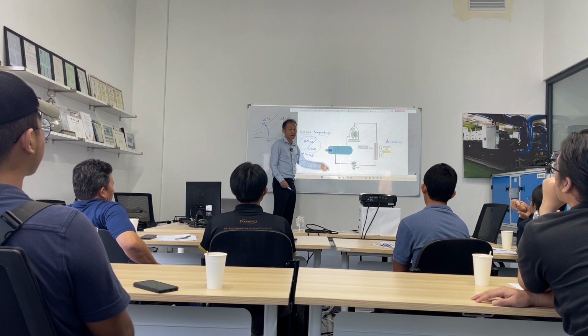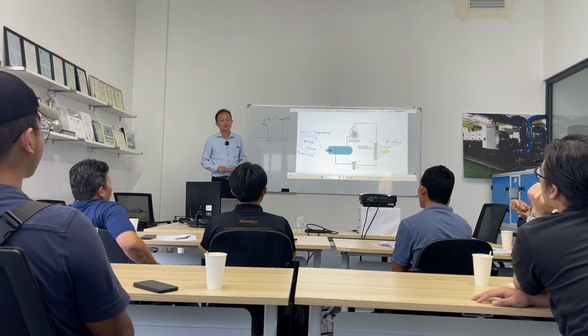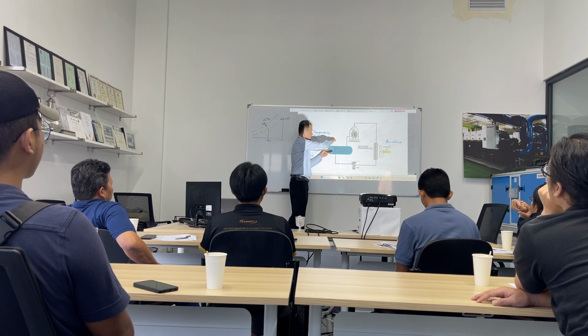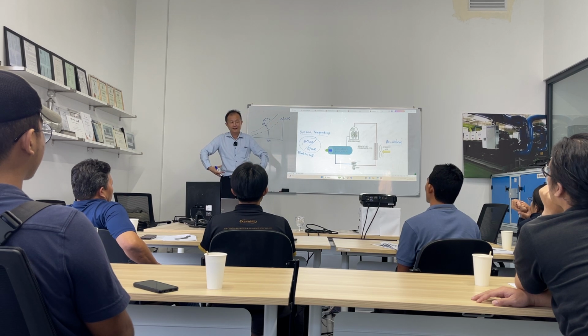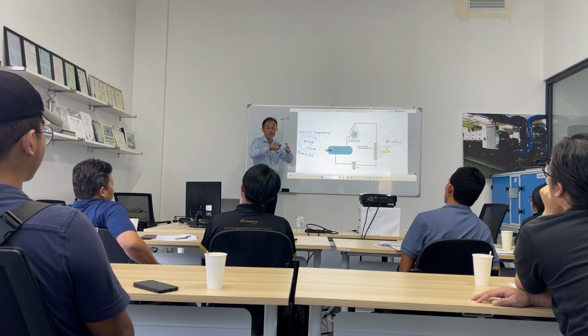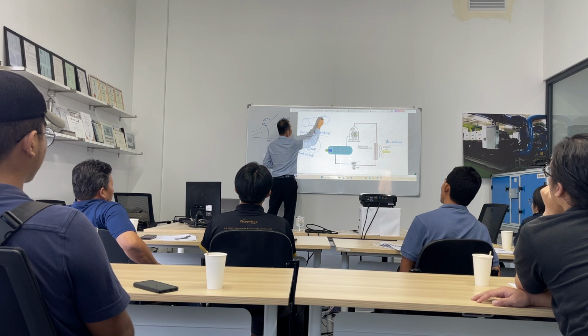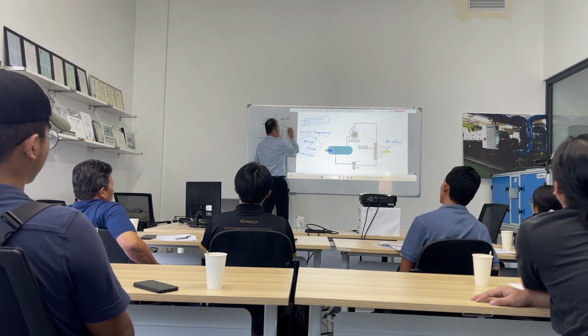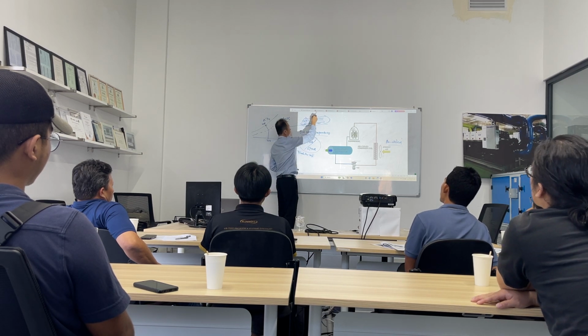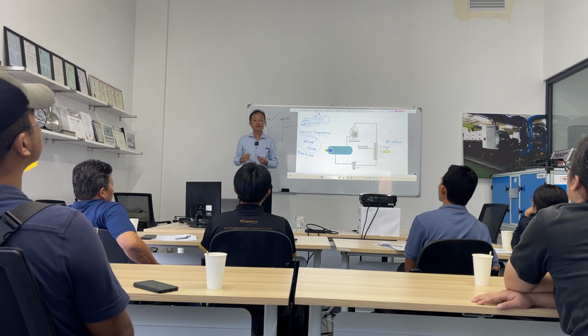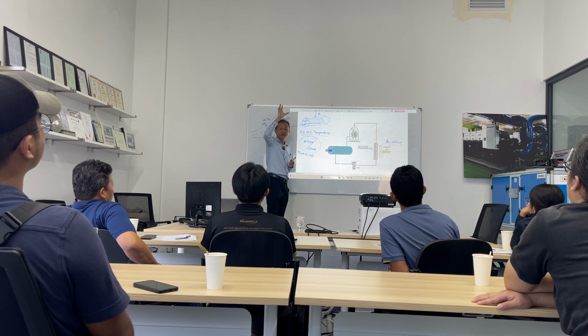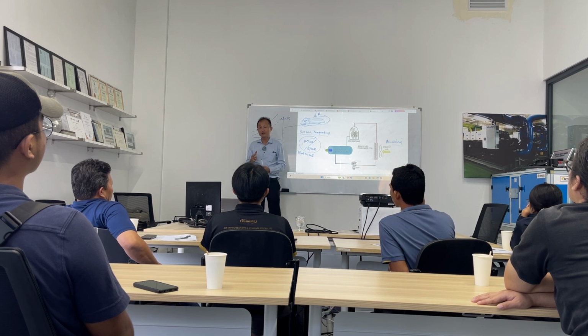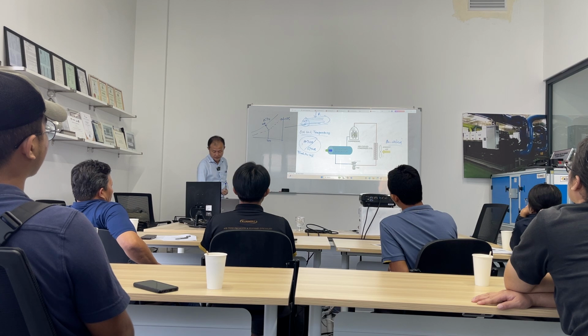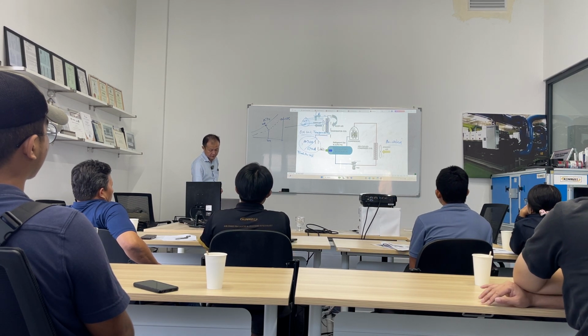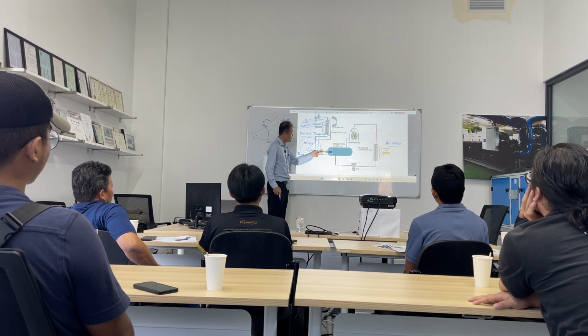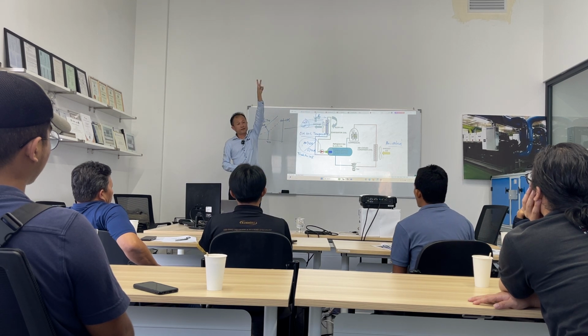Air cooled. But now if I change this component to a shell and tube evaporator. This shell and tube evaporator is a big cylindrical shell with a lot of copper tube inside it, like this. So water is circulating through the tubes, and the refrigerant is flooding the shell. If I convert the structure of this one into this one, I'm going to use it to produce water, not cooling air anymore. So I'm going to produce water and then use a pump to pump the chilled water to this coil, and then this system becomes a chilled water system.